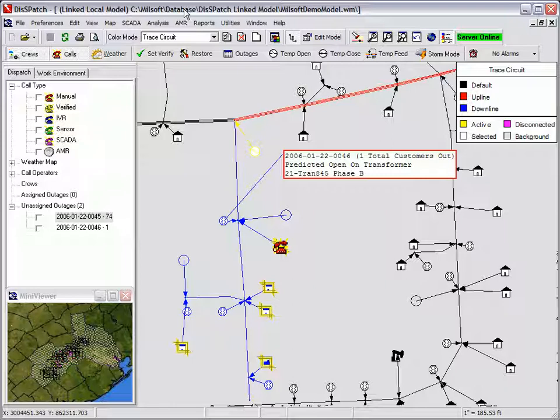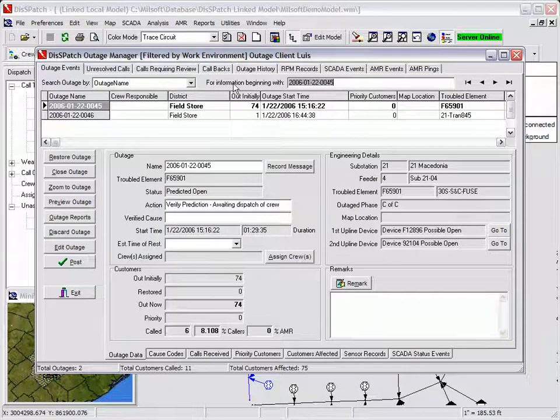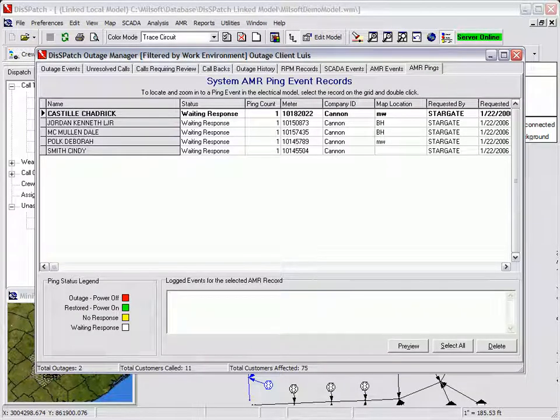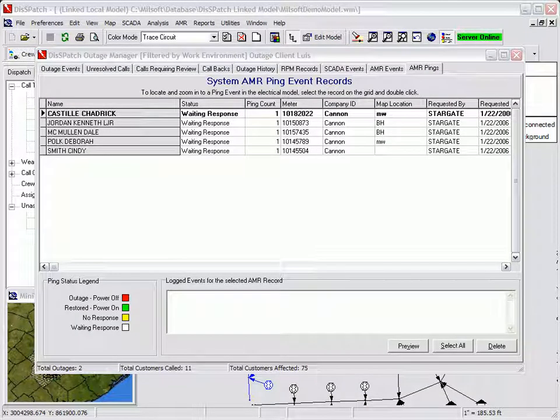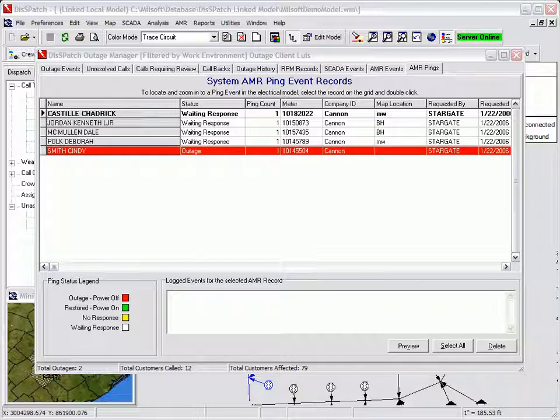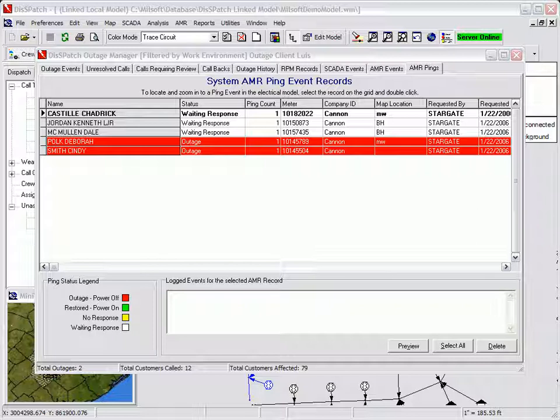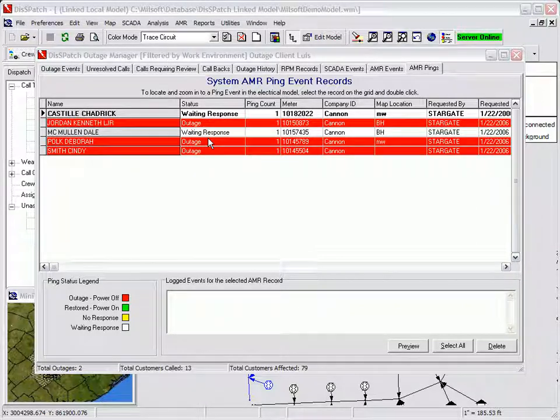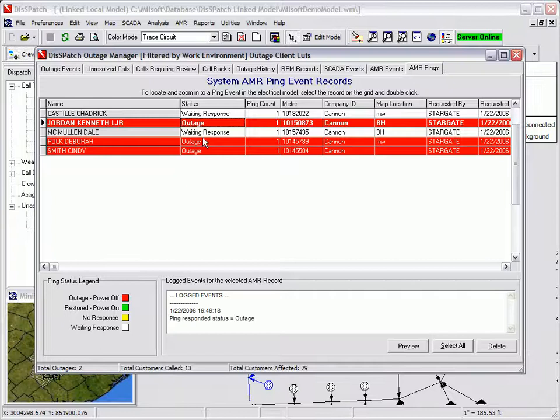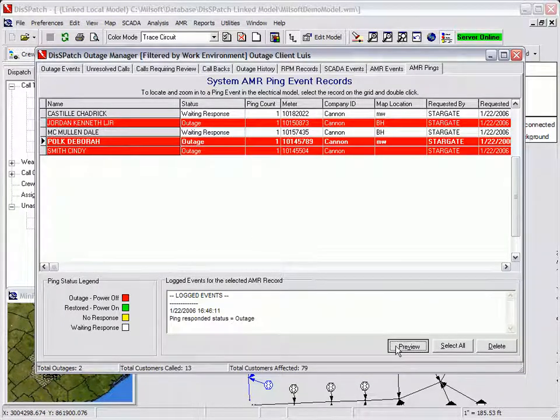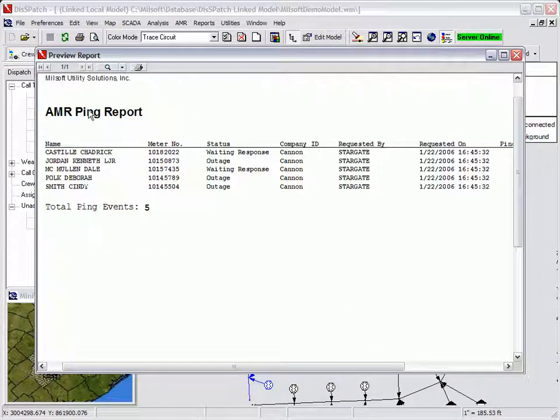The dispatcher then selects the fuse and selects to ping meters downline from the speed menu. The yellow AMR icons appear at each meter location, indicating the unknown state of the meter. When the AMR system returns information on the meter state, its color will change. If the meter has power, it will return to the normal blue state. If it is out of power, the icon will turn to red. The dispatcher can view the responses from the AMR meters in real time, either graphically or from the outage manager. The AMR Ping tab displays all the meters that are being queried. As the AMR meters report their status, the records change color to represent the status of the AMR meter. A report of all meters being queried can be printed or displayed by pressing the preview button.